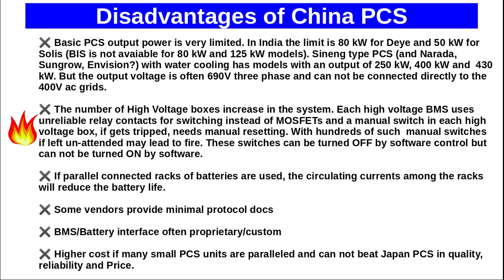The second disadvantage is that we have a minimum of 2 DC battery ports per PCS, and for n number of PCSs in parallel, there will be 2n DC ports and 2n high voltage BMSs, that is, high voltage boxes. When you have too many high voltage boxes, we have a disadvantage because each high voltage BMS uses unreliable relay contacts for switching instead of MOSFETs, and a manual switch in each high voltage box, if it gets tripped, needs manual resetting. With tens or hundreds of such manual switches, if left unattended, it may lead to fire.